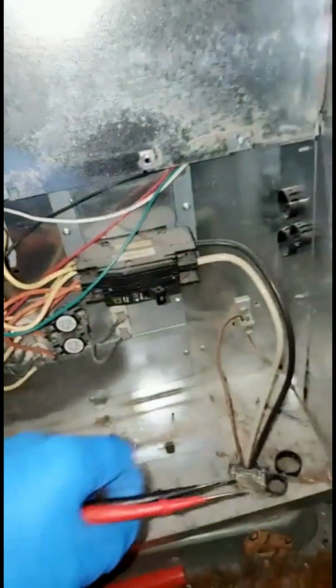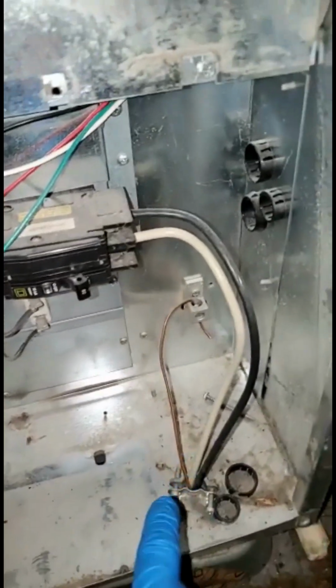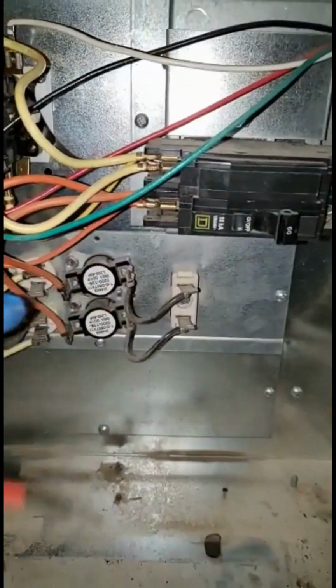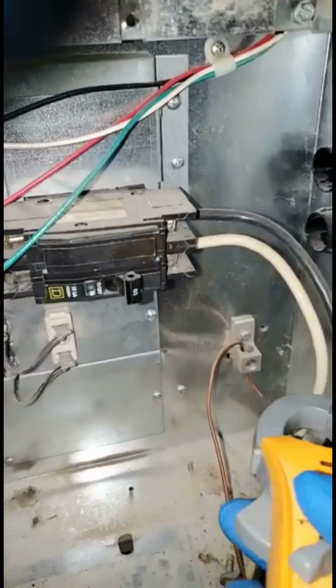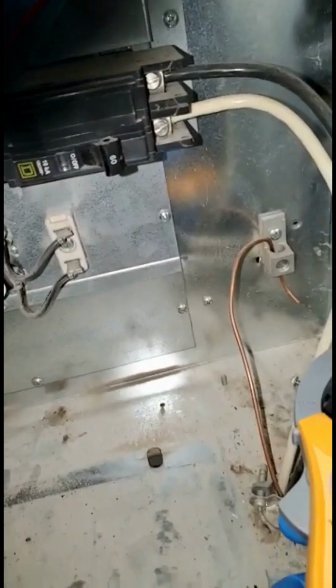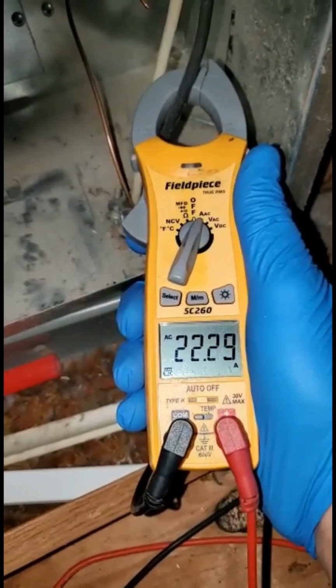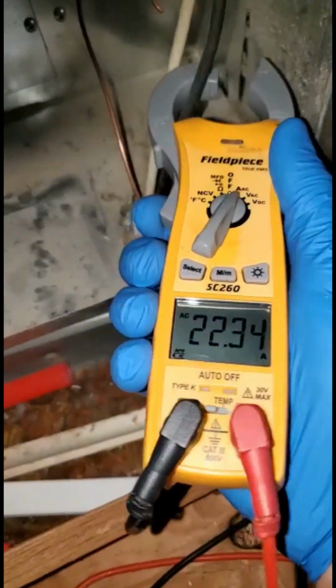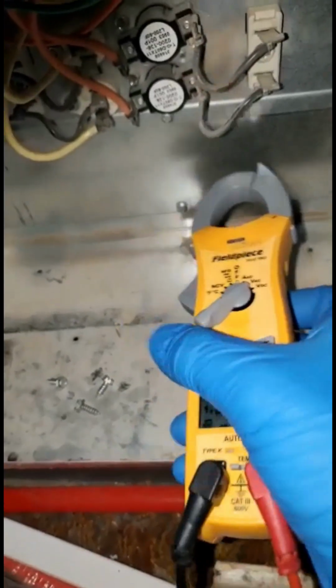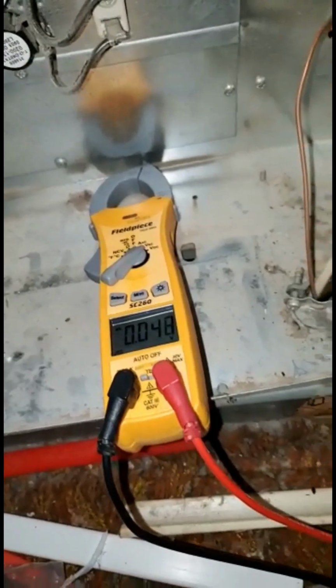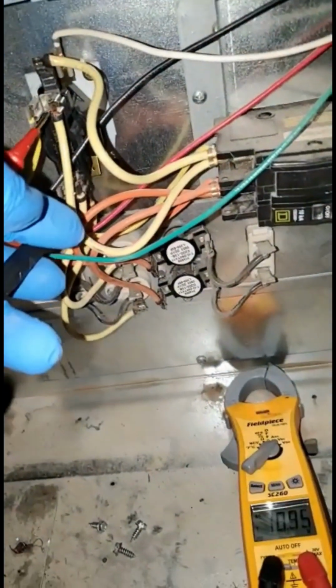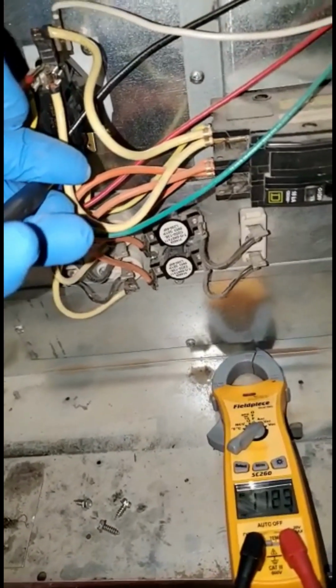And okay, so I'm working on a furnace here. You can see that we've got the power coming in. This is a 60 amp. We've got 2 kits here. That's 10 kW. I'm checking amps on this, and I'm only getting a reading of 22.3. So that means that my 5 kW is only engaged. So if I come over here and I check with my meter, I check across the top of the sequencer right here. You'll see I'm not getting a reading, which is good. That means that it's working properly.